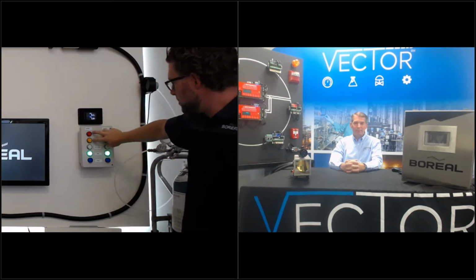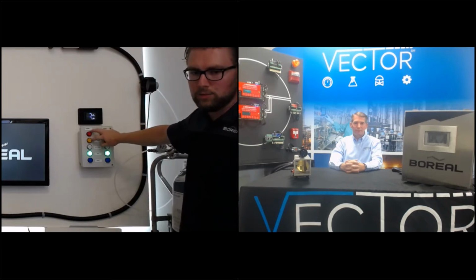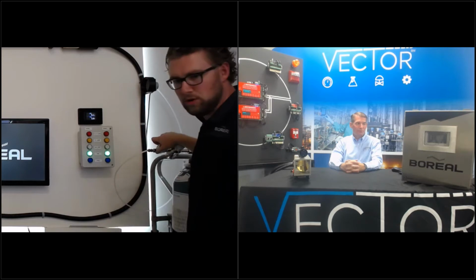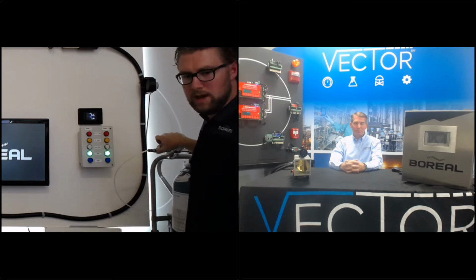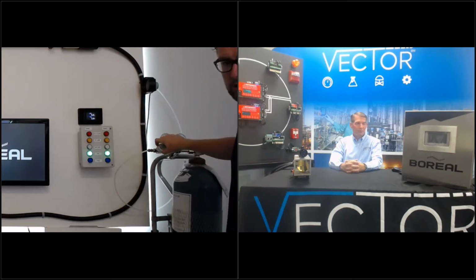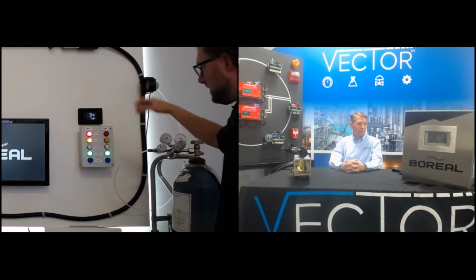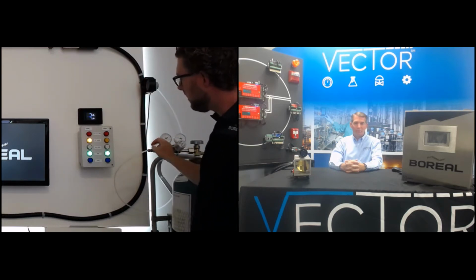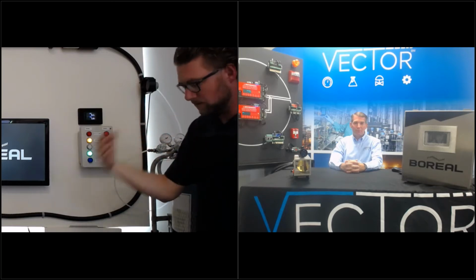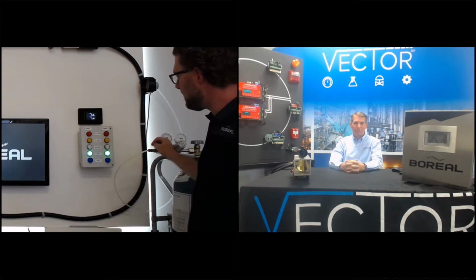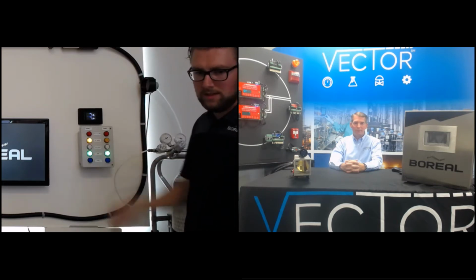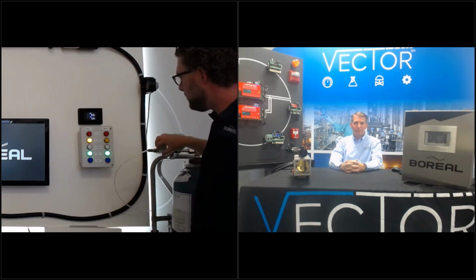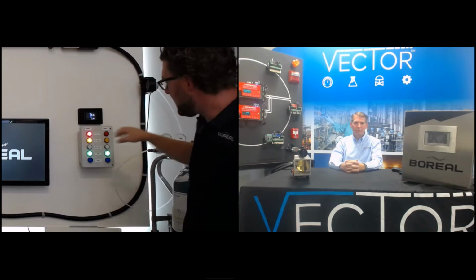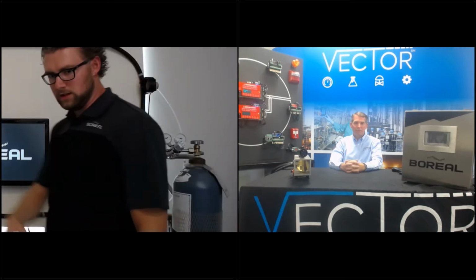to target gas. These two indicator lights here are at a high and high-high alarm threshold. And you can see how quickly this system responds to having target gas molecules present in the active measurement path. So I'll do a couple of little baby chirps and just hit the low light. We hit the low and the high at the same time here. But what is really interesting is that even when a very minute amount of methane is introduced into that active measurement path, I'll chirp it again, you can see how quickly the system responds to that as well. As we open it right up, you can see your high and high-high alarms come in. You can set your dead bands to turn off and on as and where you please as well. But this is part of the enhanced safety system.